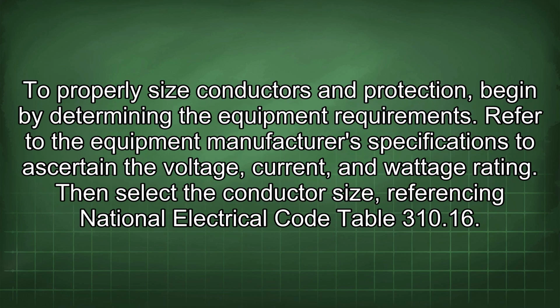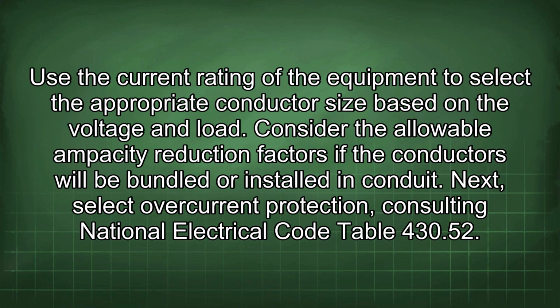To properly size conductors and protection, begin by determining the equipment requirements. Refer to the equipment manufacturer's specifications to ascertain the voltage, current, and wattage rating. Then select the conductor size, referencing National Electrical Code Table 310.16. Use the current rating of the equipment to select the appropriate conductor size based on the voltage and load. Consider the allowable ampacity reduction factors if the conductors will be bundled or installed in conduit.